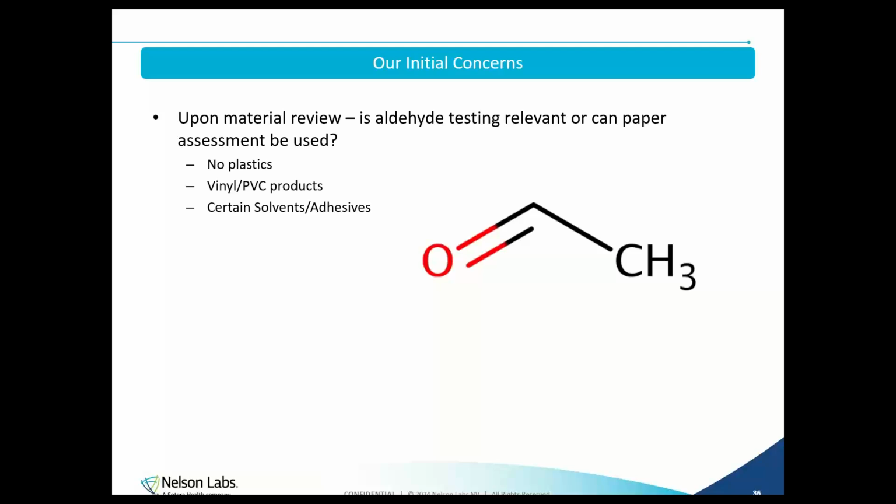Lastly, not a concern, but more of a thought process. With aldehyde testing being added to the array of tests, is this relevant for all devices, or is this adding to the burden of medical device manufacturers? Are we able to omit aldehyde testing in general if a thorough paper assessment on materials and construction happens? If certain adhesives used as solvents or binding are used, then aldehyde testing should be completed. But if a device has a safe material history where aldehyde release is basically impossible, can this testing be omitted?